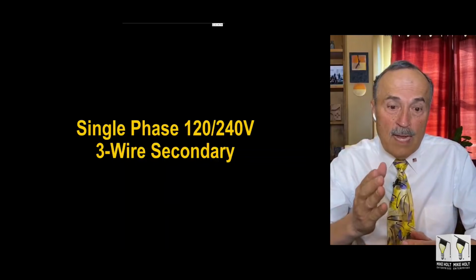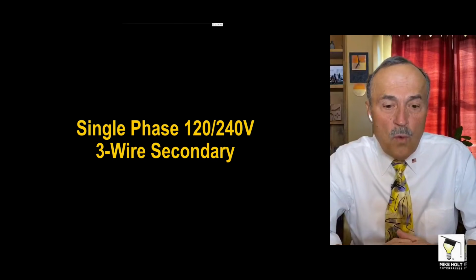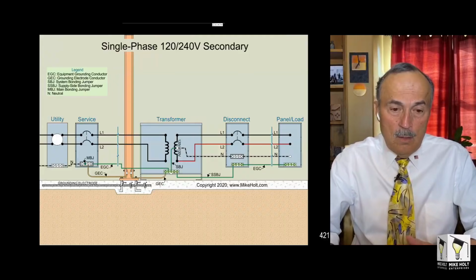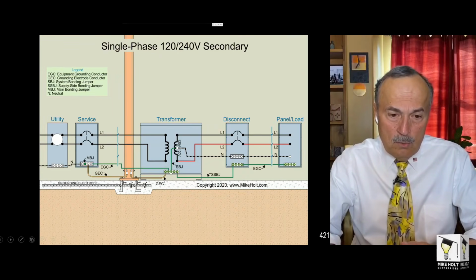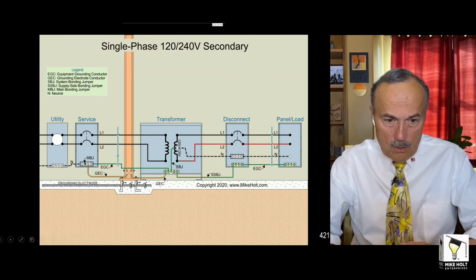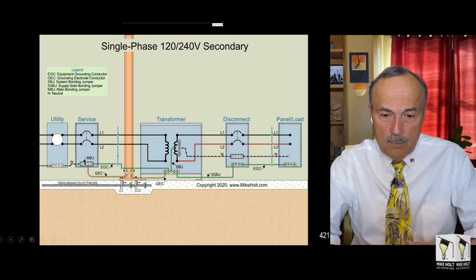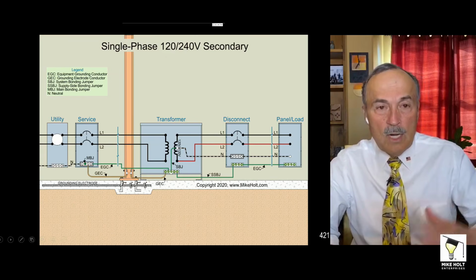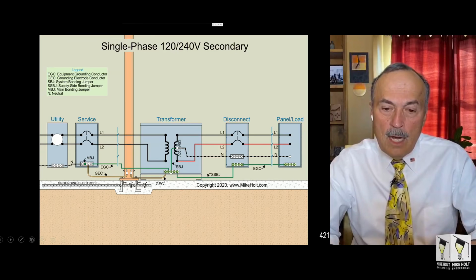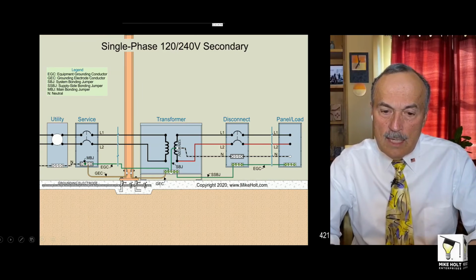Quick, go real fast. Single phase, 120/240 volt, 3-wire system. You bring a line 1, a line 2. I don't see my neutral here. Oh, okay, we're just bringing a single phase to the transformer. That's a primary, whatever the voltage is, we don't care. 120/240 on the secondary.